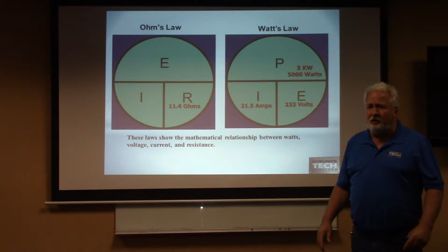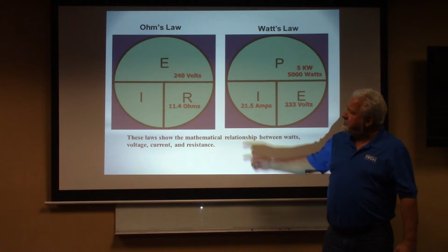Well, what if I found a heat strip in the truck or supply room, and I measured the resistance on it? If it came out to 11.4 ohms of resistance, and I applied 240 volts to that, I can tell you what the amperage is going to be: 21 amps. If I'm going to get 21 amps at 240 volts, any idea what kind of heat strip that might be? 5 kW? It would be a 5 kW heat strip. You just identified that.